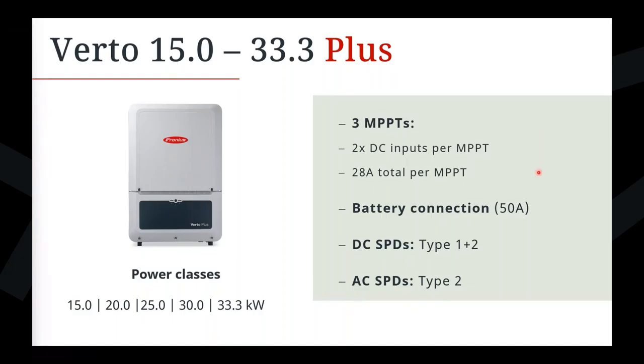Each input can convert 28 amps, so that's the usable current. Just note that's a maximum of 28 amps for each tracker, right? So you do have the 2 DC inputs, but per tracker, it's a maximum of 28 amps. And they have a short circuit current of 50 amps, so a lot of flexibility there, and you can parallel strings. The battery connection is also 50 amps, so it allows for those high charge and discharge rates, which I'll show you on the next slide. It comes with integrated DC and AC surge protection devices.